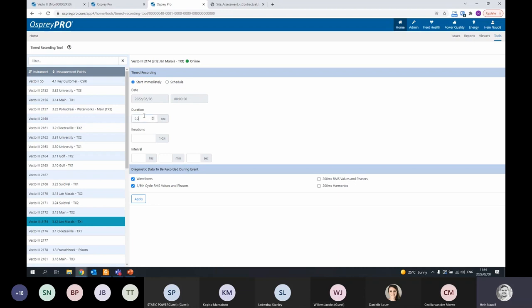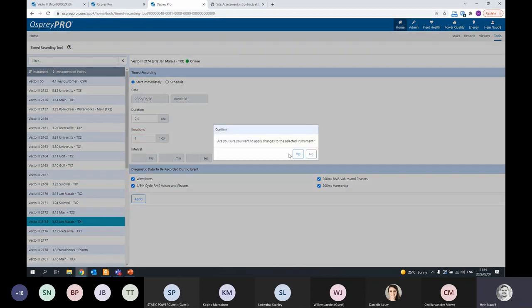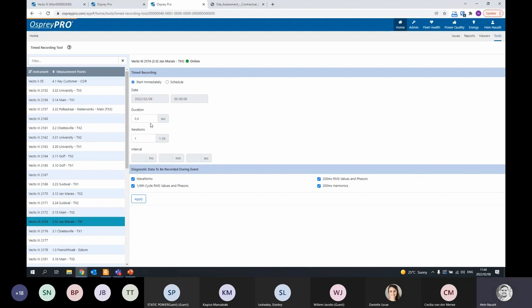Let's just make this a bit longer. I'll set how many times it needs to do this recording, the interval, and what data needs to be recorded. I'll set that to one interval, and I want to record everything. So now if I do this, it's going to take 0.4 seconds. It's going to do a timed recording for 0.4 seconds of the waveform, and store that data for you. So if you give it time, I can show you that data under events.